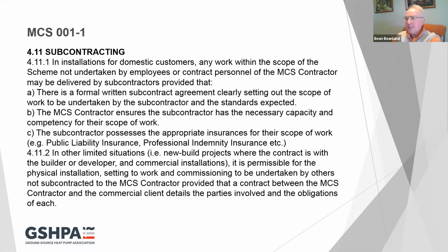So if an MCS certified contractor has some subcontractors working for them, either doing part of the actual MCS equipment install, or, for example, doing underfloor heating, or providing the drilling or the trenching contract, if that is in your contract as an MCS certified installer, you are required to have a formal written subcontract agreement. That is end of.